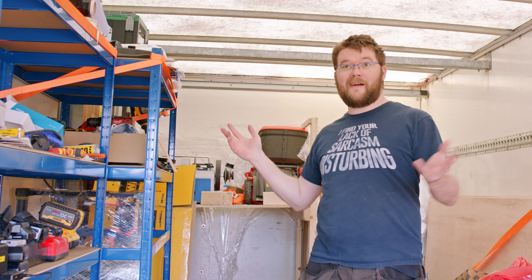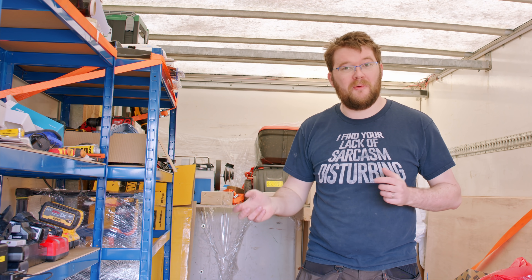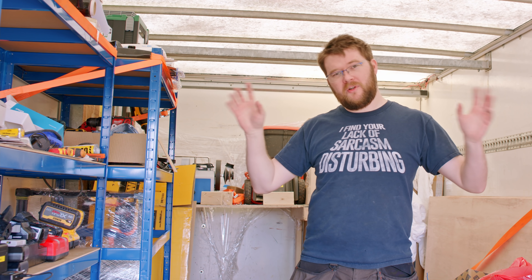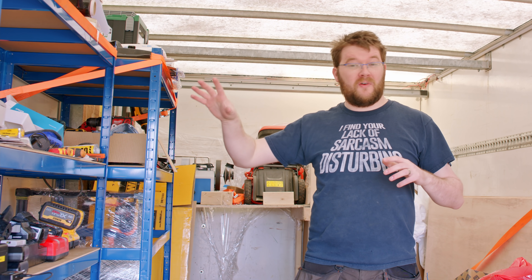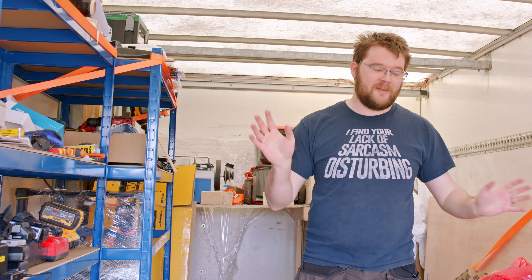Hello and welcome back to the truck which is outside the mill. We've got a bit of a problem — we keep getting our power boards wet. When we're steam cleaning, water goes kind of everywhere and we've tripped the earth fault protection circuits in our breaker box a number of times in a day, consistently at times when things just get splashed. So we want to make some power boards and extension leads which are waterproof.